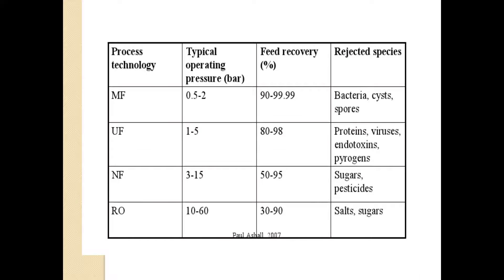Looking at process technology — typical operating pressure, feed recovery, and rejection. The typical pressure for microfiltration is 0.5 to 2 bar. For ultrafiltration it is 1 to 5 bar. For nanofiltration it is approximately 3 to 15 bar. For reverse osmosis it is 10 to 60 bar. Feed recovery: microfiltration gives 90 to 99.9%, ultrafiltration gives 80 to 98%, nanofiltration gives 50 to 95%, and reverse osmosis gives 30 to 90%.